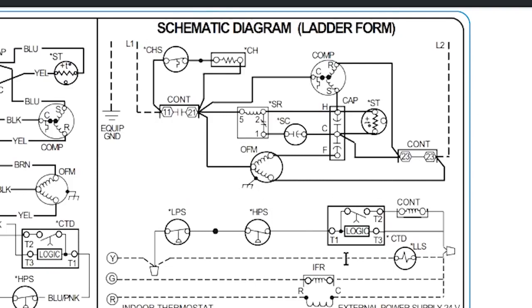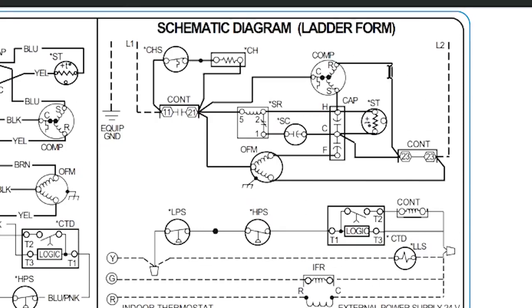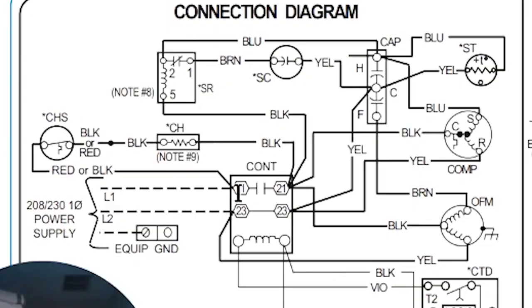You don't see the transformer feeding into L1 and L2 here because this low voltage is coming from another power supply — the transformer is on the inside in a typical residential split system. We're only showing the 24-volt side. The squiggles on the other side would be the input power to the transformer, but we're not showing that. So this is our 24-volt side, and this is our 240-volt high voltage side.